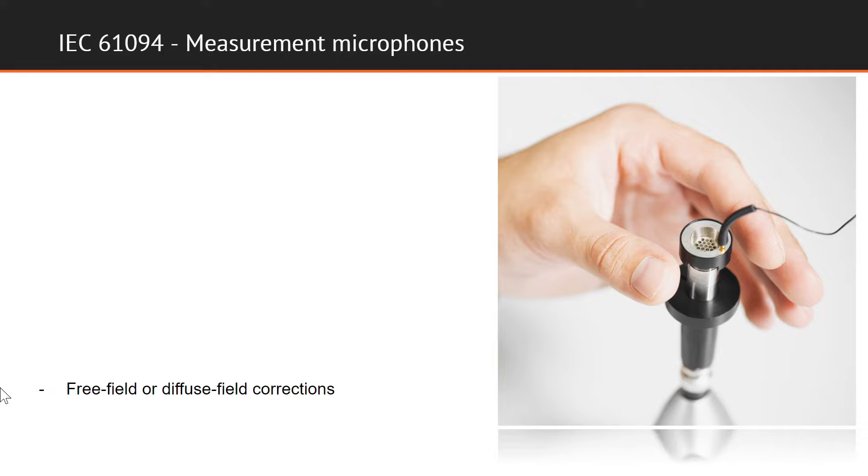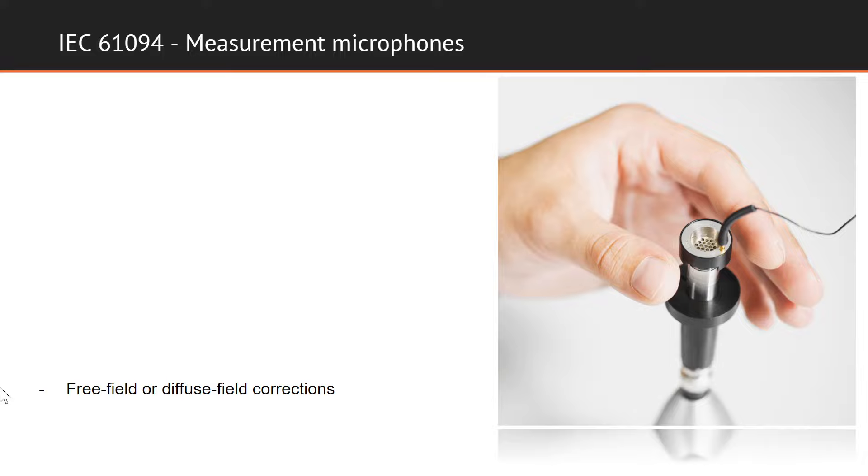Depending on the type and application of the microphone, free field or diffuse field corrections may be added to achieve the required type of frequency response. When it comes to sound intensity measurements, we carry out measurements utilizing a special piece of equipment called the intensity probe. There is a specific IEC standard for calibration of intensity probes. Let's take a look at how this is performed and why it is important.